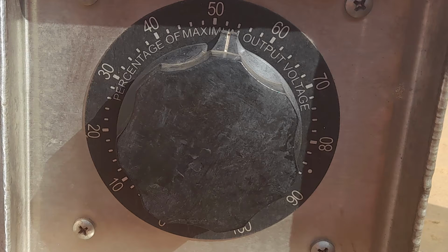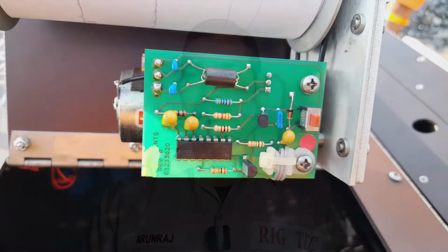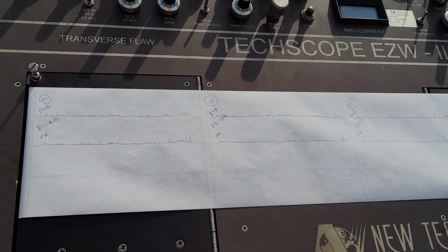Check the variac, the potentiometer or mag control, whether it is 0 or the cable is loosened or broken. And next is to check the chart, just run and off. If the chart is working, it's okay. It means the chart is moving from right to left. There is a chart take up, a chart receiver, that will wind the chart. Coil is okay. Chart is moving.